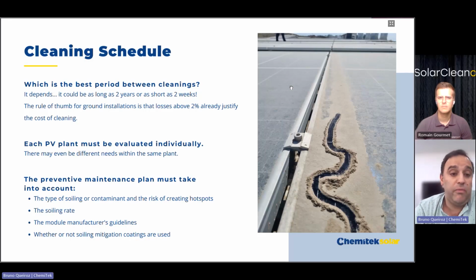Even though, as I told before, the rule of thumb for ground installations is 2%, because it is the point where, usually on the utility scale, cleaning becomes financially viable. It makes sense to clean because you will pay for the cleaning with the gains that you'll get. Of course, the cleaning schedule needs to take into account the type of soiling that you have, the soiling rate, how much you are losing every month, the guidelines of the manufacturers, which are also important to follow, and whether you are using soiling mitigation coatings or not. Soiling mitigation coatings can help you extend the time between cleanings, but can also be used as prevention to make cleaning easier and not change the cleaning period, so to speak.